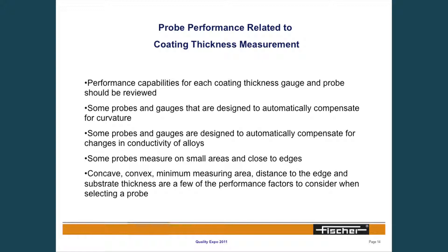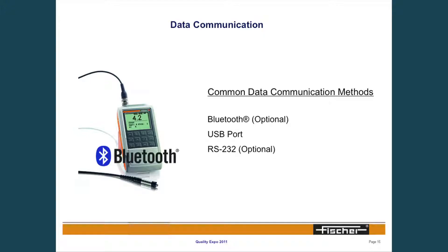One of the major technological advancements over the last several years has been the data communication of handheld instruments. The price and capabilities of these handheld instruments with data output has drastically improved. We're getting more for less, and I would encourage people to take advantage of that data output to help control their process. The typical data communication methods are Bluetooth, USB, or RS-232.